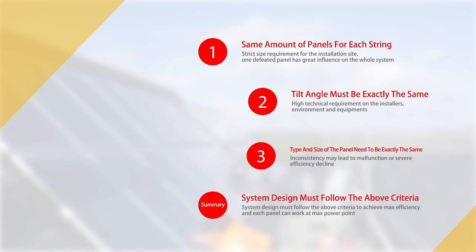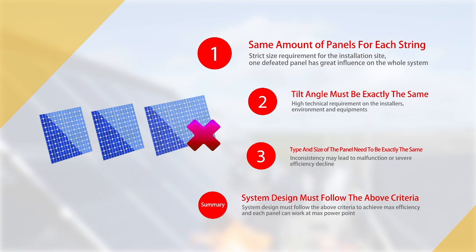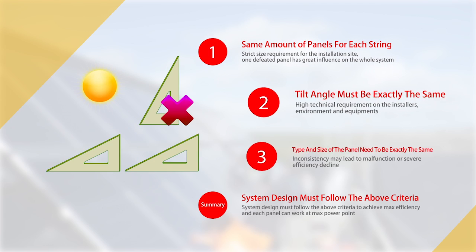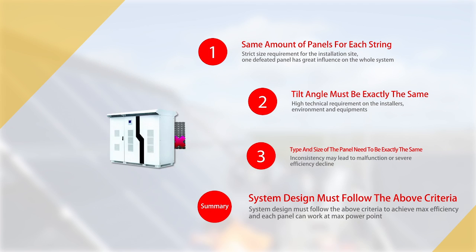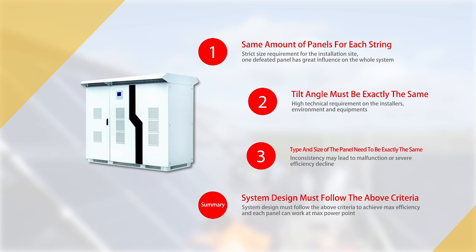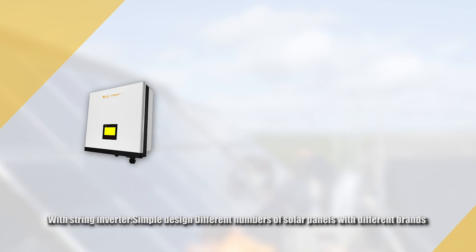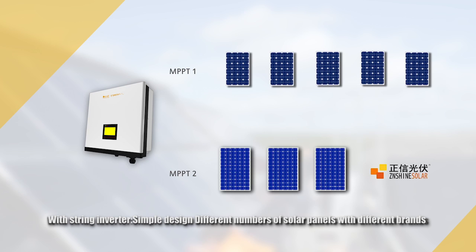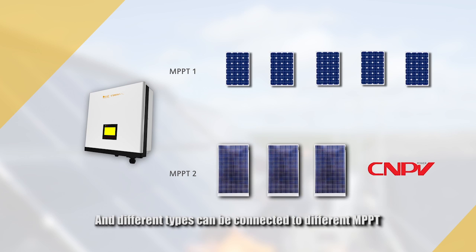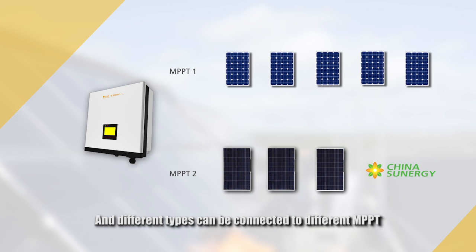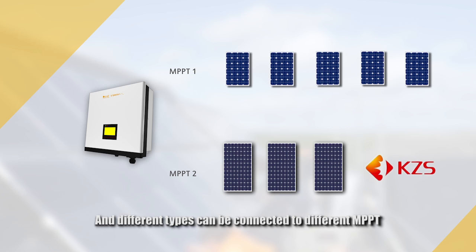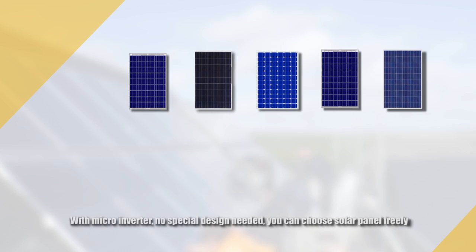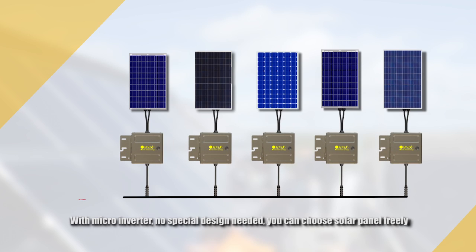Regarding flexibility in system design: central inverters require complex design with inflexibility. To ensure that each string of solar panels works at the maximum power point, the number of panels, tilt angle, panel type, and size of each string must be exactly the same. With string inverters, the design is simple — different numbers of solar panels with different brands and types can be connected to different MPPTs. With micro inverters, no special design is needed at all.